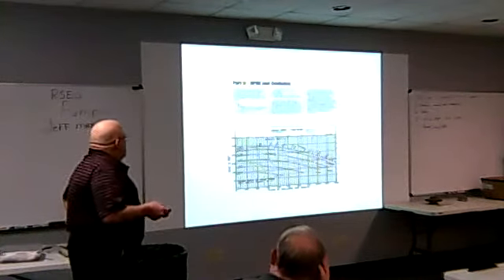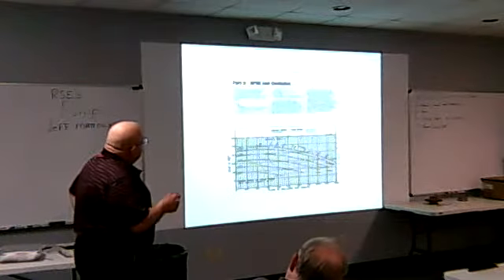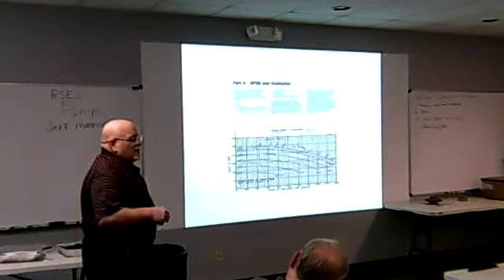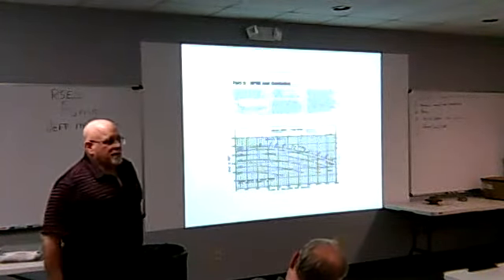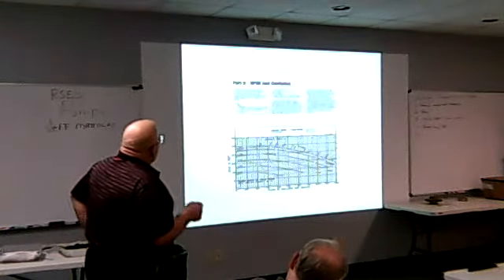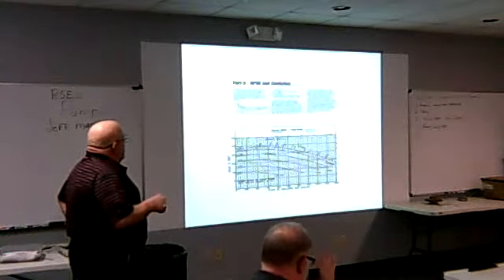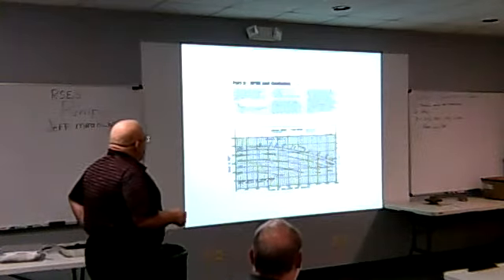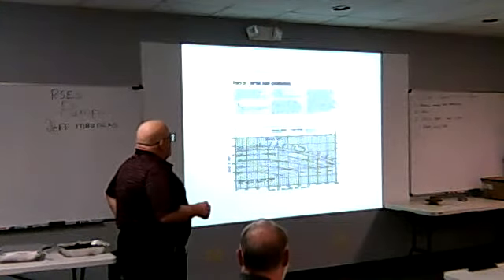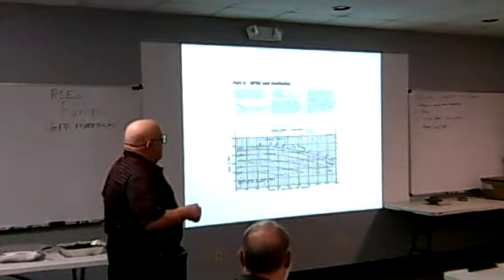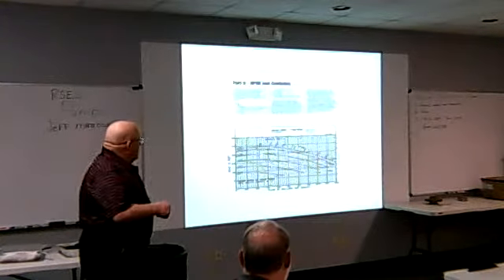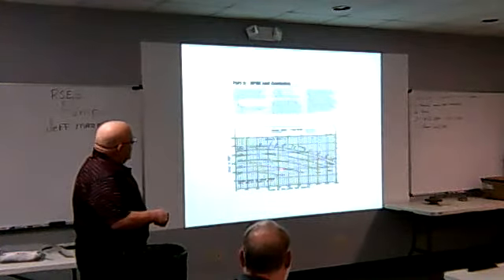Cavitation. This is a big thing. This comes into play more and more on my steam system, high temperature systems. I'll explain why in a second. This is the NPSHA calculation. On every pump curve, see these numbers up here? This is called net positive suction head required.